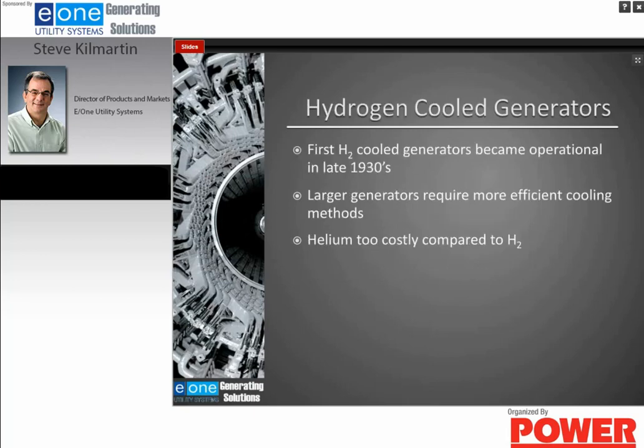In the late 1930s, there was an increased demand to get more megawatts out of the generators. With generators, more megawatts means more iron. They got to get bigger. And also more heat is generated as you increase your megawatts. In order to satisfy the demand for power without increasing the physical size of the generators, a different method was needed to cool the generators. I find it very interesting that someone decided it would be a good idea to cool a generator with a flammable gas like hydrogen. However, the idea worked, and now all large generators are cooled, at least to some extent, with hydrogen.